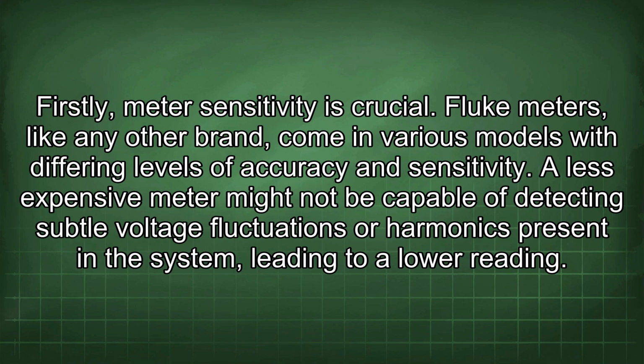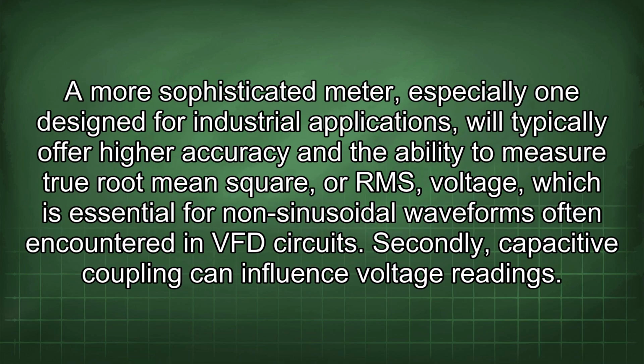Fluke meters, like any other brand, come in various models with differing levels of accuracy and sensitivity. A less expensive meter might not be capable of detecting subtle voltage fluctuations or harmonics present in the system, leading to a lower reading. A more sophisticated meter, especially one designed for industrial applications, will typically offer higher accuracy and the ability to measure true root mean square, or RMS, voltage, which is essential for non-sinusoidal waveforms often encountered in VFD circuits. Secondly, capacitive coupling can influence voltage readings.